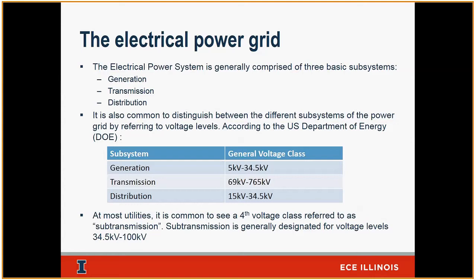So this table is from DOE. That's how it's defined in the DOE world. Generation is 5 kV to 34.5. Transmission is 69 kV to 765. And distribution is 15 kV to 34.5. So you can see 34.5 to 69 is another subcategory that we call sub-transmission.